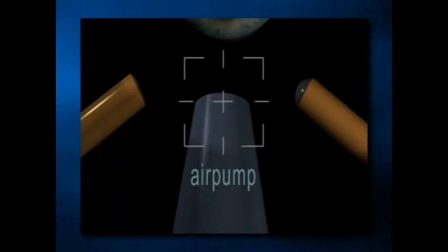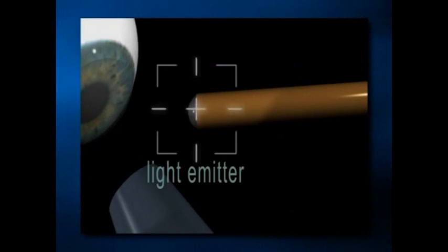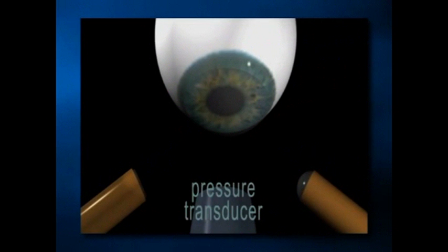There are four key components to the applanation system of the Ocular Response Analyzer: a solenoid-driven air pump, an infrared light emitter, a light intensity detector, and a pressure transducer. At the start of the test sequence, the infrared light emitter directs a beam of light onto the cornea.